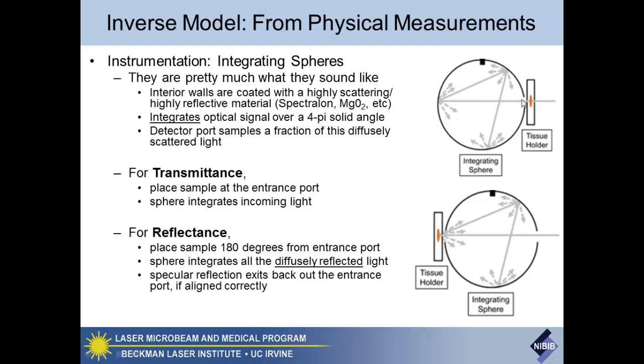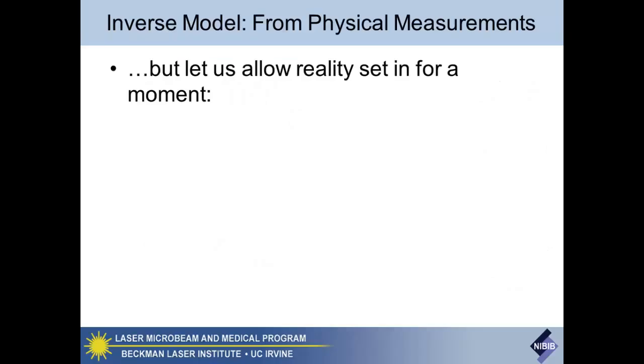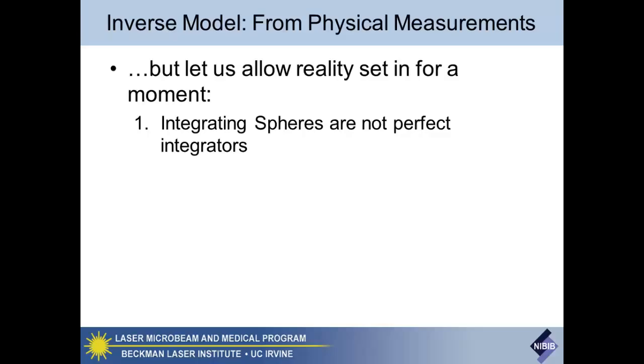Going back to the physical measurement: you have this integrating sphere. The idea is that by having a sphere that's very white — usually Spectralon on the inside, a rough surface, acting like a diffuse, highly reflective scattering agent — it will be able to integrate any light from any angle transmitted through the sample. Likewise, for reflectance, if you send the light straight through, any light that exits the sample at any angle will be reflected and integrated within that sphere itself.